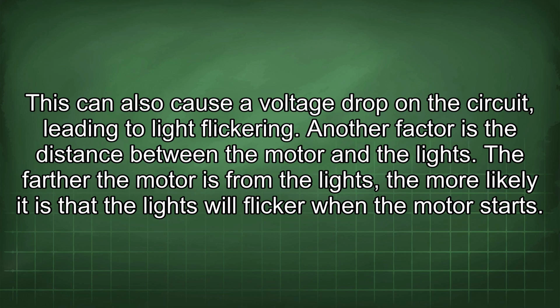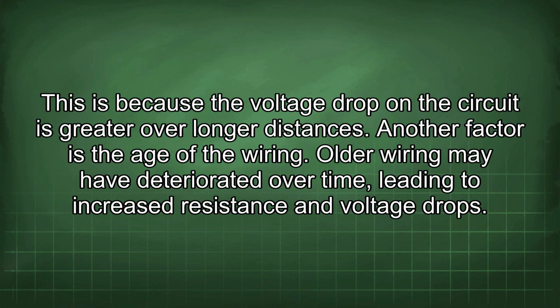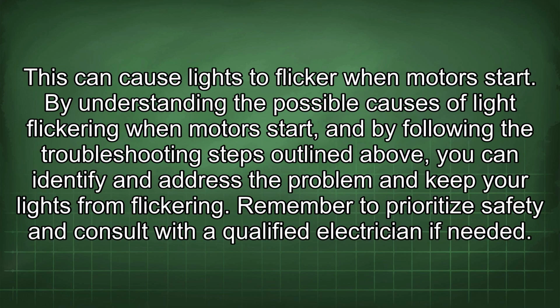Another factor is the distance between the motor and the lights. The farther the motor is from the lights, the more likely it is that the lights will flicker when the motor starts. This is because the voltage drop on the circuit is greater over longer distances. Another factor is the age of the wiring. Older wiring may have deteriorated over time, leading to increased resistance and voltage drops. This can cause lights to flicker when motors start.